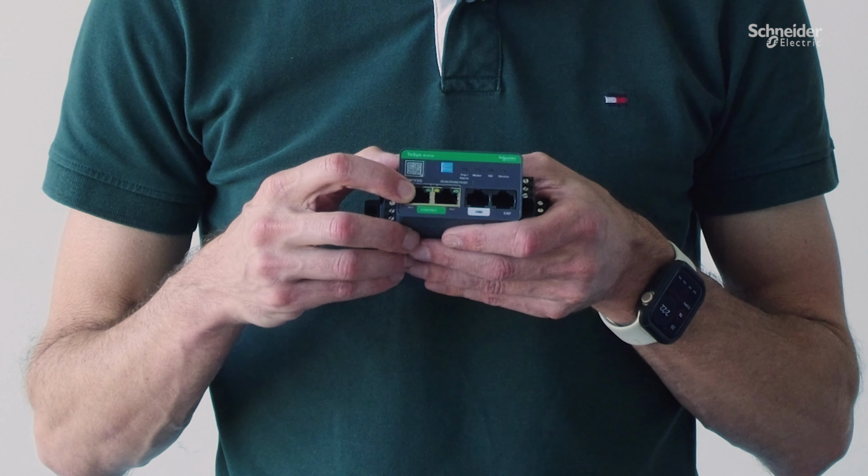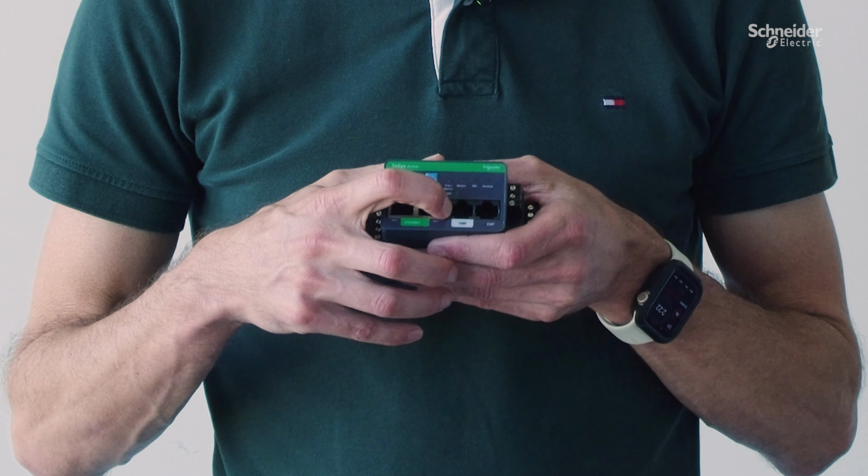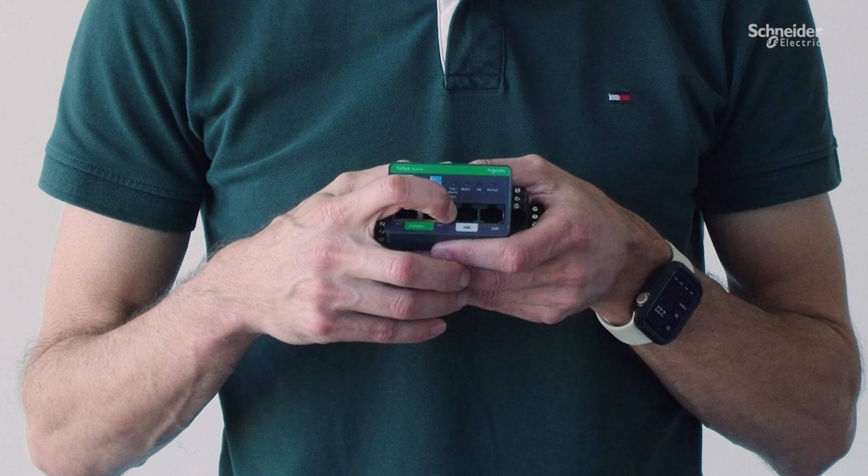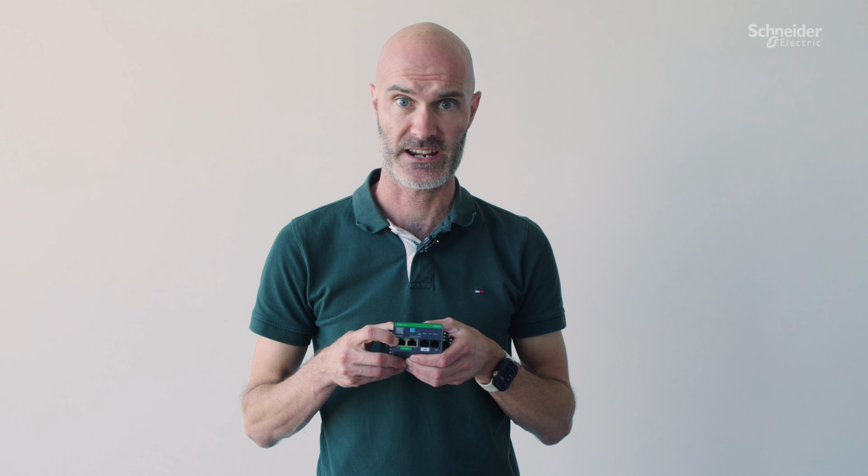What we're going to be looking at today is how to take a brand new TeSys Tera and give it its initial IP address. If we take our unit, like I have here, we're going to be using the inbuilt Ethernet ports to start with, or we're also going to be looking at the HMI port combined with the LTMTCUF HMI unit. When we use the inbuilt Ethernet ports, we're going to be using its default IP address, which is calculated from its MAC address, whereas as described before, with the HMI, we'll just be using the actual HMI unit and the keypad on the front.